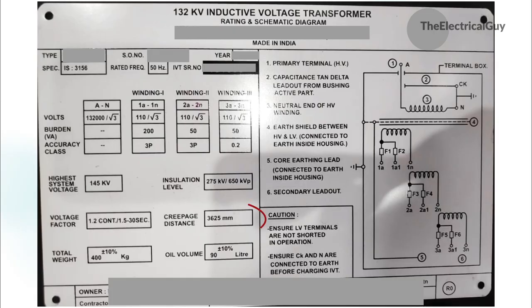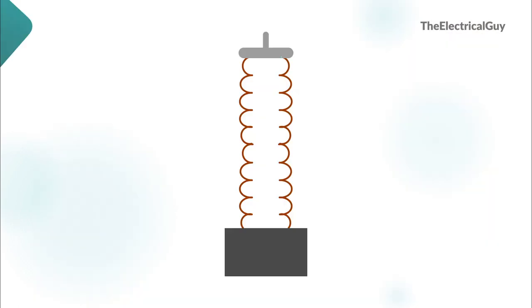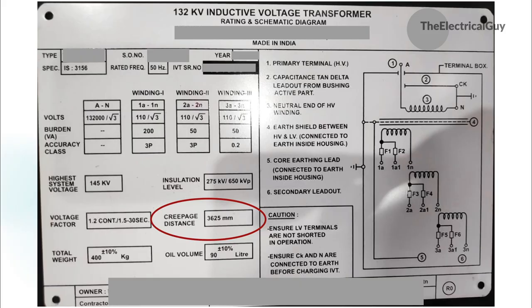Next is creepage distance, which is the shortest distance between two conducting parts along the surface of insulation. There are two types used: 25mm per kV and 31mm per kV. 25mm per kV is used majorly, while 31mm per kV is used where there is high pollution, like in cement industries. So if you multiply 145kV by 25, you get 3625mm, which is the value mentioned on our nameplate.